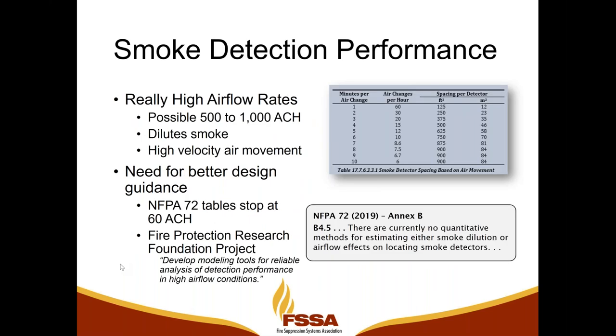Now, I would be remiss if I didn't speak a little bit about smoke detection as we talk about aisle containment. NFPA 72, the National Fire Alarm and Signaling Code, guides us in applying smoke detection to data centers. There is a table that you may be familiar with that has the air change rates in it and the adjustments to the spacing per detector. Many data centers are being built today with air change rates higher than what are covered by the table.